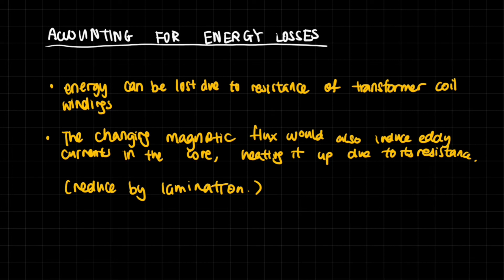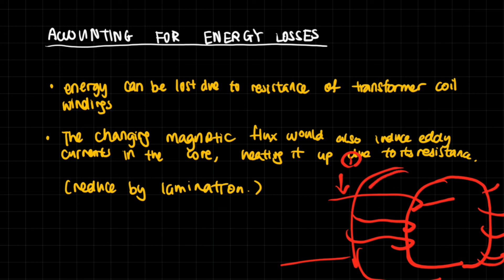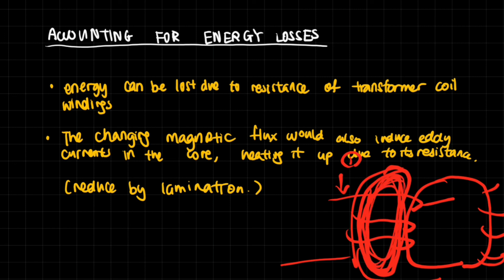Energy can also be lost in transformers. First, there is resistance within the coil windings themselves. Second, the changing magnetic flux induces eddy currents within the iron core — the core is also a conductor — and these circular currents grow larger and larger. A high current means a high amount of heating, so you can lose significant energy due to heat dissipation.